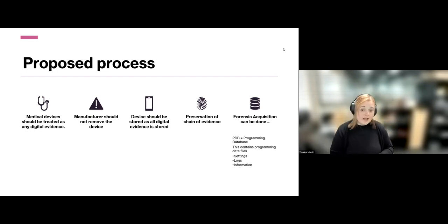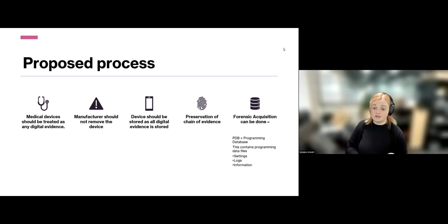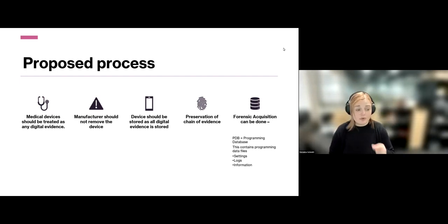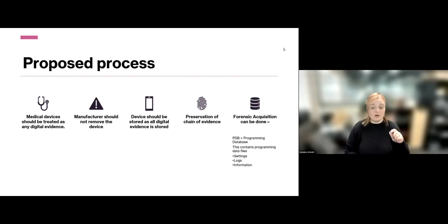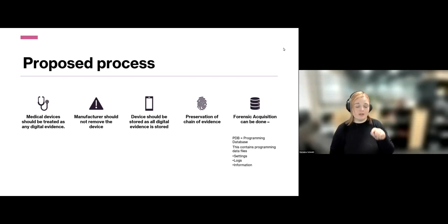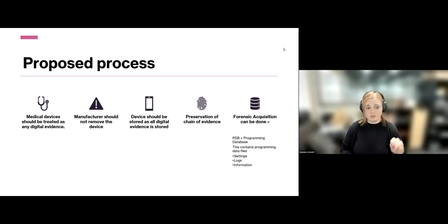Once this is done, you can do a forensic acquisition on these devices. They are slightly different—if you wanted the raw information, you would get this from a PDB file, which is the programming database. Contained in this is all the programming data files, including settings, logs, information, therapies, patient information, when the device was programmed, how it was programmed, and when it was updated, as well as firmware. So the PDB file, or programming database file, is the file that contains all this information.